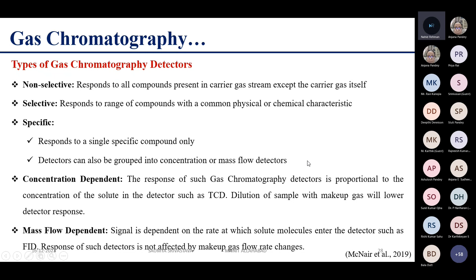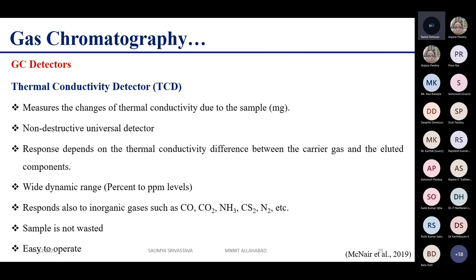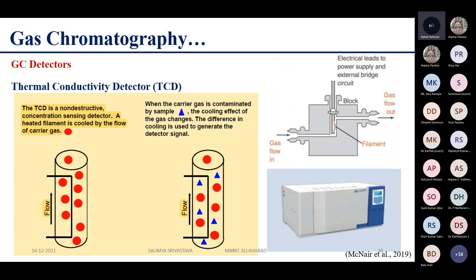Many types of detectors are there. First is the thermal conductivity detector, which measures the changes in thermal conductivity due to the sample, and it is a non-destructive universal detector. Its response depends on the difference in thermal conductivity between the carrier gas and the eluted components. It has a wide dynamic range, and it also responds to inorganic gases such as carbon monoxide and carbon dioxide. The sample is not destroyed in the thermal conductivity detector, and it is easy to operate. The thermal conductivity detector changes with temperature, hence the associated current changes due to the change in thermal conductivity, which is ultimately reflected in the form of peaks on the chromatogram.